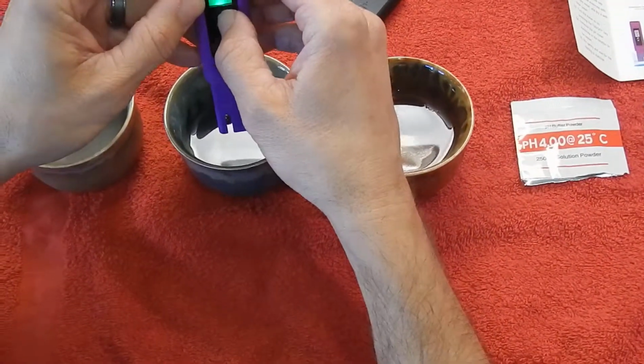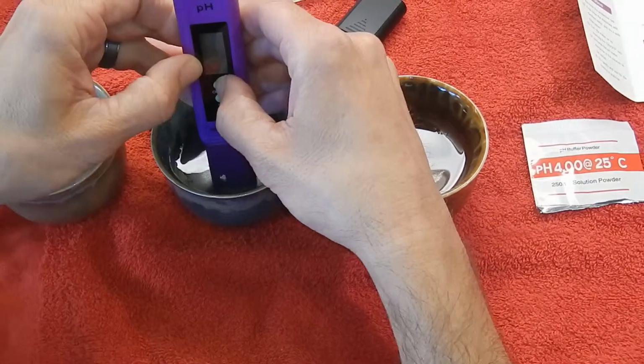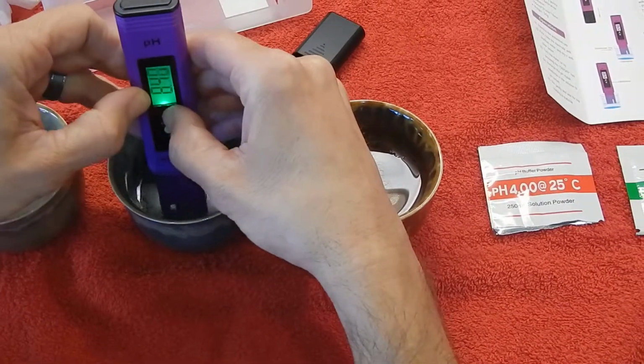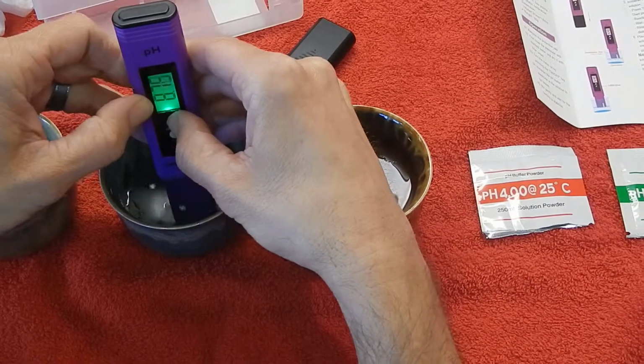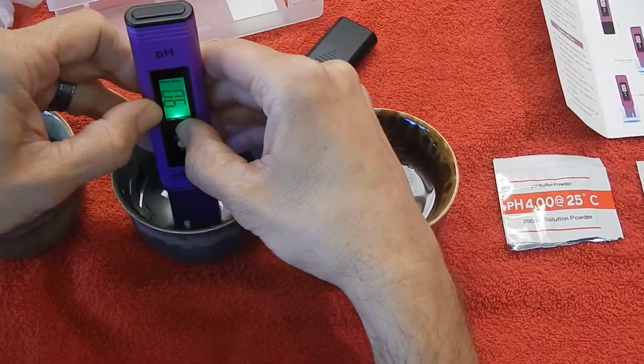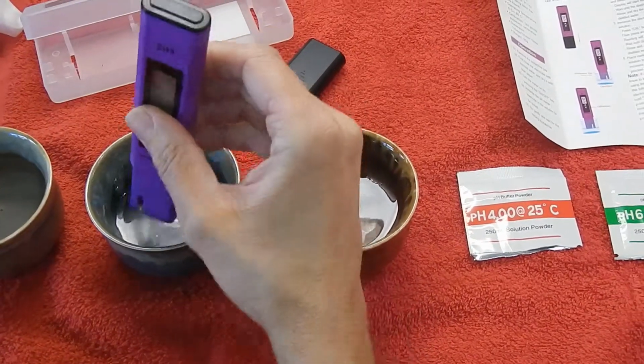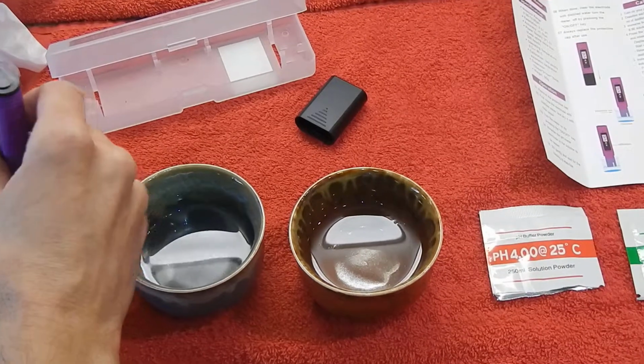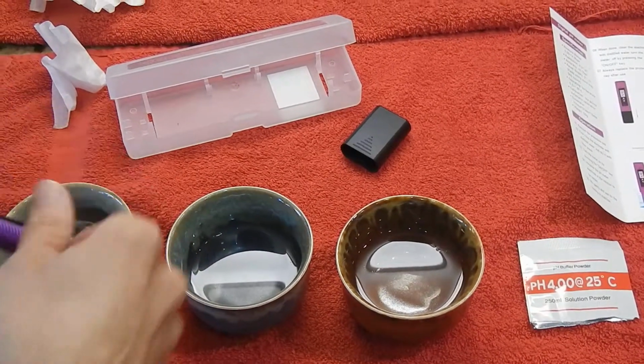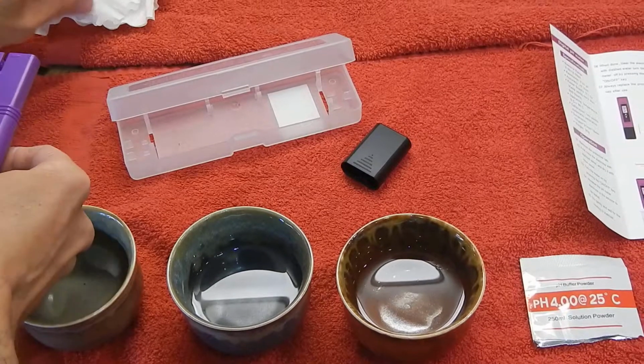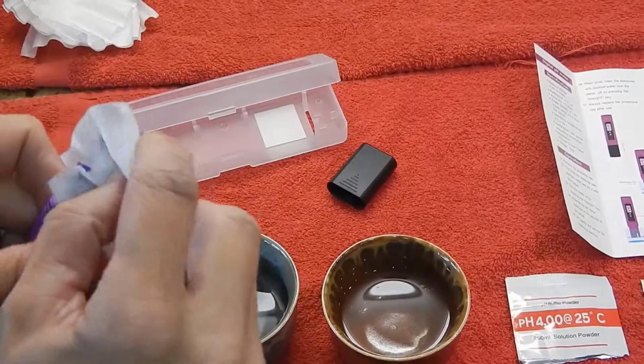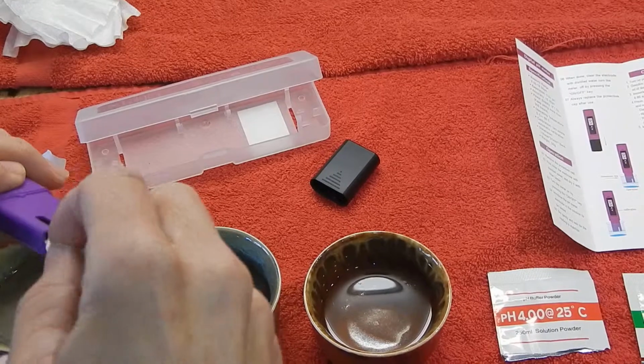So to use it, you just take the device, put it in the solution, press the on button, and gently stir it. I think you want to keep air bubbles off the device, or off the electrode. And as you can see here, it gives you a pH reading. In this case, it's at 9. So then, once you're done using it, you dip it back in the distilled water solution, rinse it carefully, get a filter, and blot it dry again.